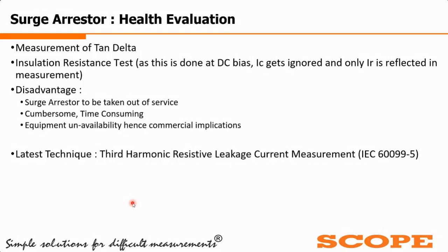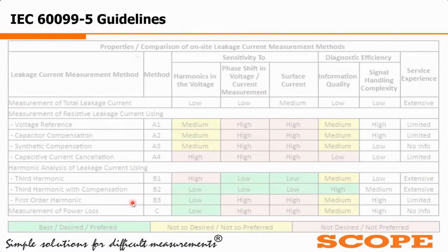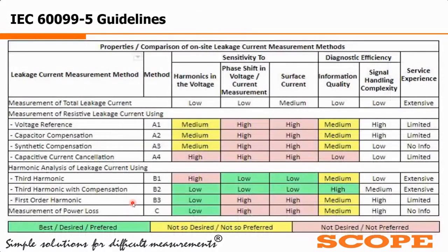So the latest technique which is coming into the picture is third harmonic resistive current measurement, which is recommended by the IEC 60099-5. Though it is a very big document and a lot of people will have access to it, this is a snapshot of what has been told. In the IEC guidelines, a total of 8 methods of measurement have been prescribed or described. They are named A1, A2, A3, A4, and B1, B2, B3, and C.